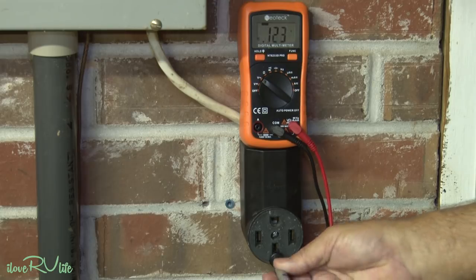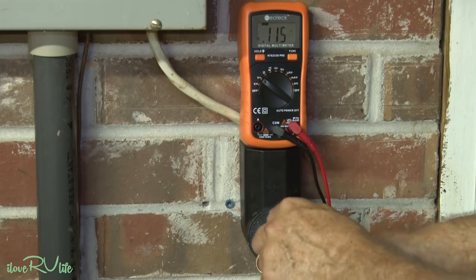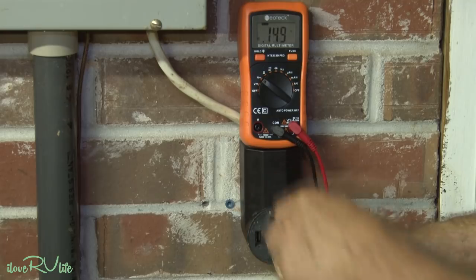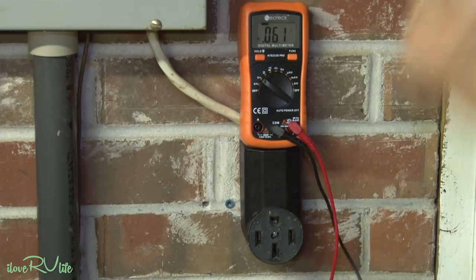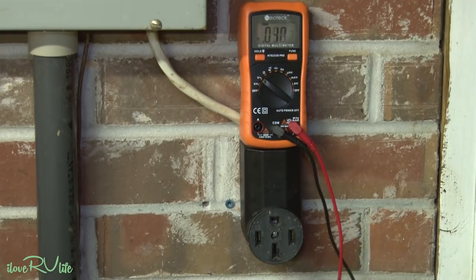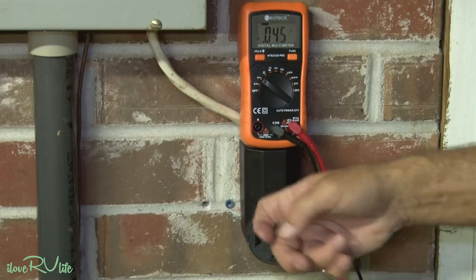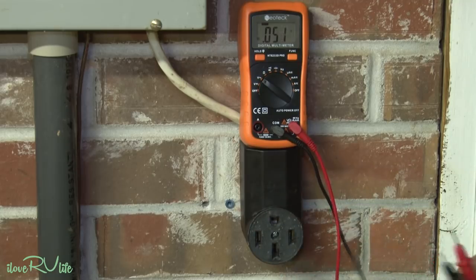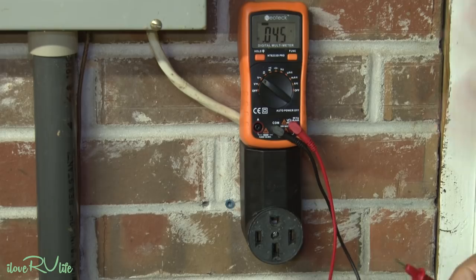So this is a great way to test it to ground and see if you've got any voltage. If you have voltage there, whether it reads 40, 50, 60, 70, 80 volts, it doesn't matter. If you see voltage on the side of that, run to your camp host and say, I've got a problem with my plug, I've got hot skin. And if they don't come running and don't want to remedy it, my suggestion is go to another campground. That's just the bottom line, it's not safe.